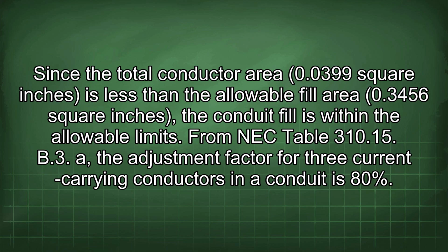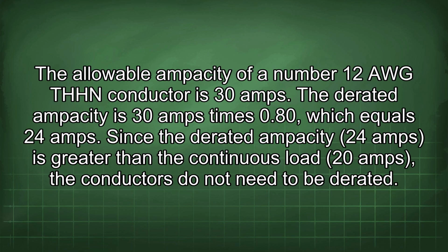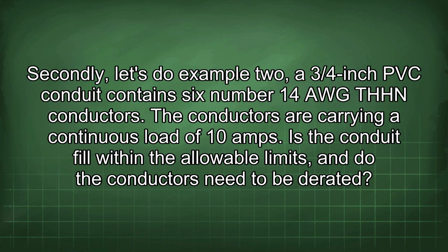From NEC Table 310.15. The adjustment factor for 3 current carrying conductors in a conduit is 80%. The allowable ampacity of a number 12 AWG THHN conductor is 30 amps. The derated ampacity is 30 amps times 0.80, which equals 24 amps. Since the derated ampacity 24 amps is greater than the continuous load 20 amps, the conductors do not need to be derated. Secondly, let's do example 2.